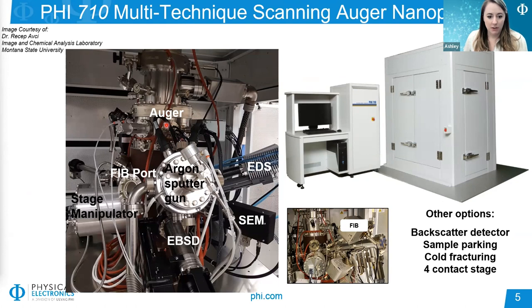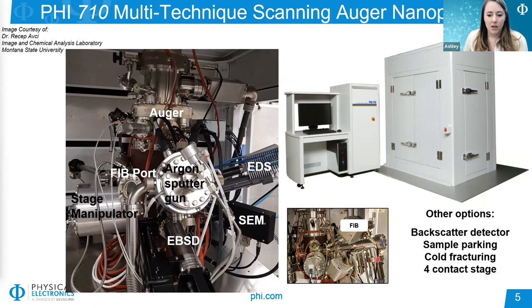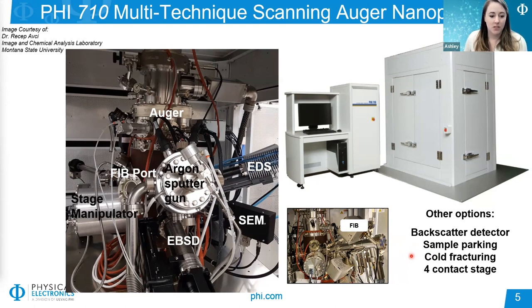In addition to its primary function, the AES instrument also has several in-situ attachments available, including options to add an EDS, EBSD, and backscatter detectors. We also have an in-situ focused ion beam (FIB) available on the system, as well as other options for sample handling such as a parking wheel allowing you to park up to six platens in vacuum, a sample fracturing device for cold fracturing at liquid nitrogen temperatures, and a four-contact stage that allows for electrical measurements to be made in-situ.